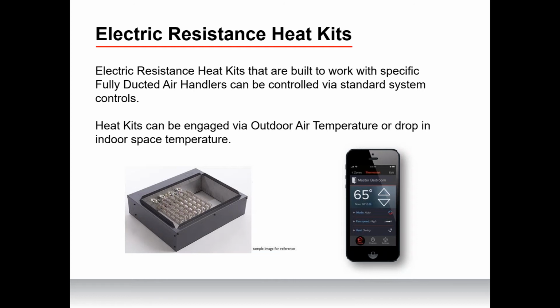I always say, and if anyone is on here that I work with on design applications, I don't see the attendee list, but if there's anyone on here that I currently work with, you can attest to this. If you are putting in a fully ducted air handler solution in the Midwest, just put an electric resistance heat kit on it. It doesn't hurt, right? For the cost to add on a simple piece like this, the control strategy is so simple, especially if it's the same manufacturer. So if you're putting a Mitsubishi air handler in, you're putting in the Mitsubishi heat kit, they integrate seamlessly together. It's worth putting it on just for the peace of mind of an emergency backup solution, even if you don't necessarily need it.